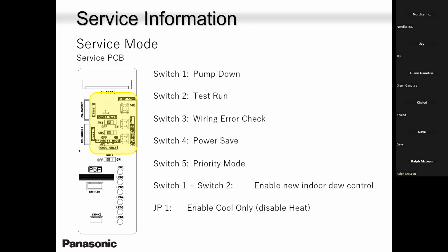Basically, I've worked with test run from the time I have joined Panasonic, and the test run I use is for troubleshooting. Test run tells me a lot of things like low on gas, or sensor has gone weak. So basically we put the unit in test run cooling or test run heating, depending on the day, the temperature and the season. And when we put on the test run, we read the running amps. We also check our pressure, if our pressures are good or bad.